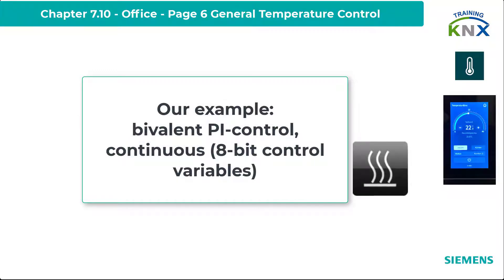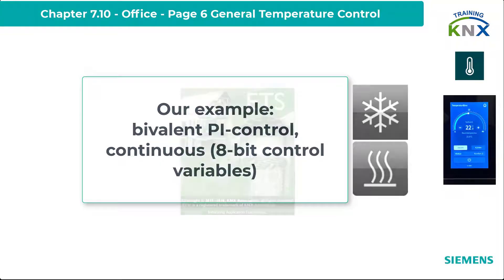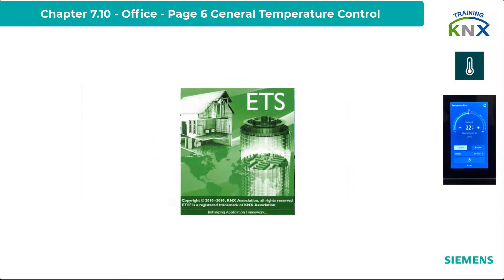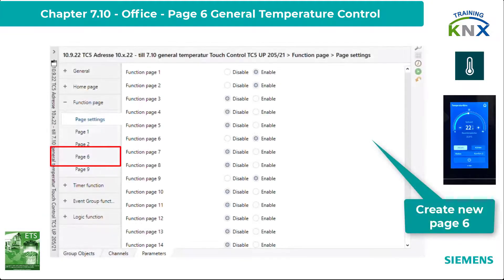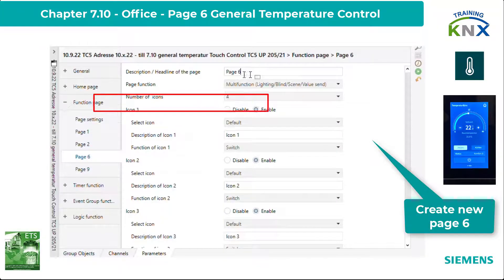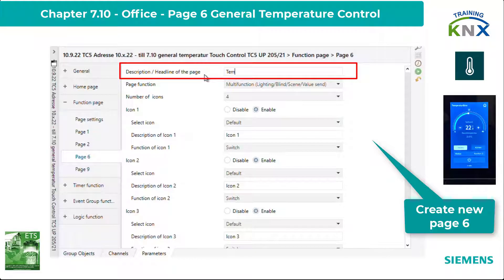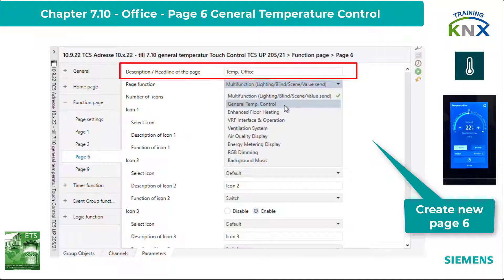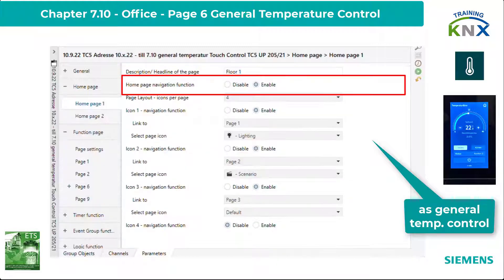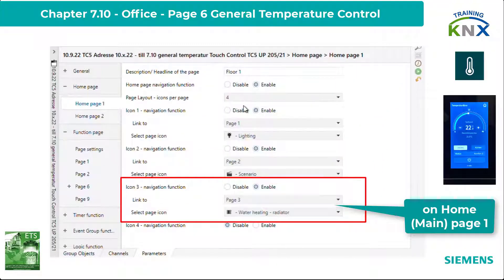That is the option where both a heating and a cooling circuit are controlled separately. First, I create again a new page in the parameters: function page 6. I assign the appropriate heading — 'Temperature Office' — and page function: General Temperature Control. This page is included as a third call on the main page 1.